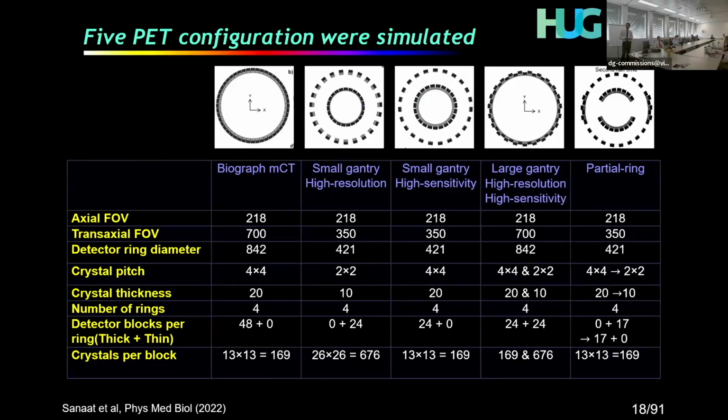it led us to, for example, in this scanner, okay, you can see when we are using the thin crystals, it brings us the high resolution, and when we put the thicker one, it brings the high sensitivity. So in this case, we actually address this trade-off.